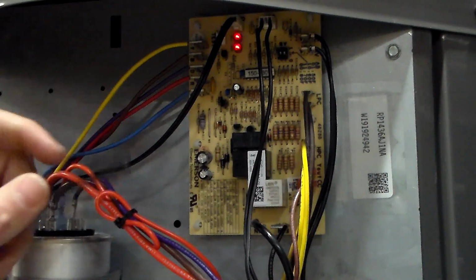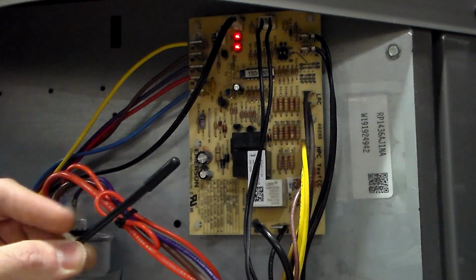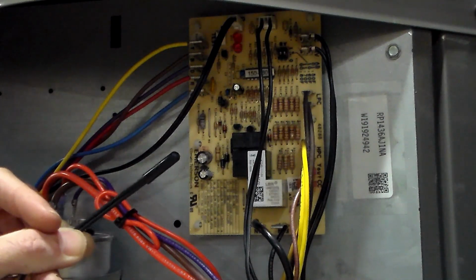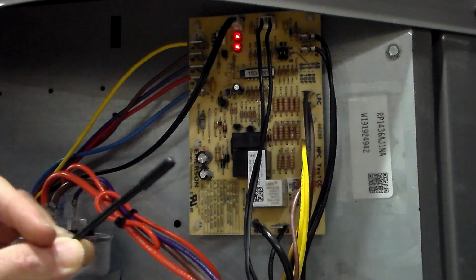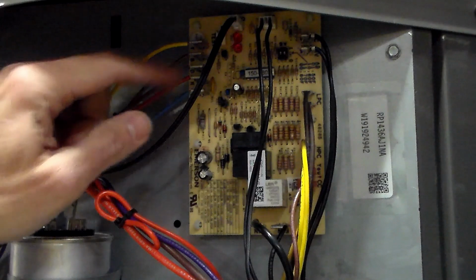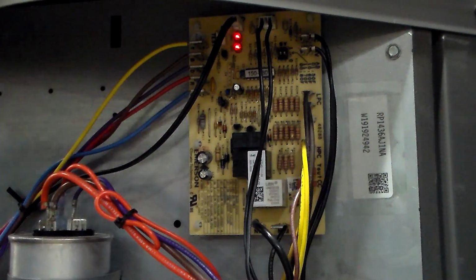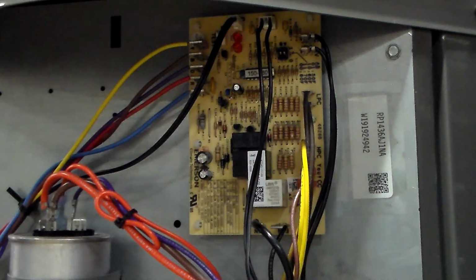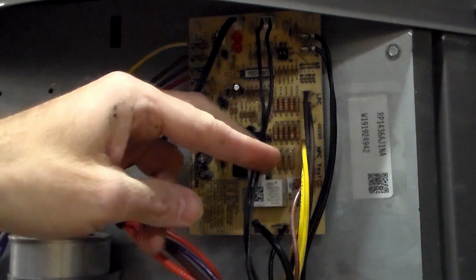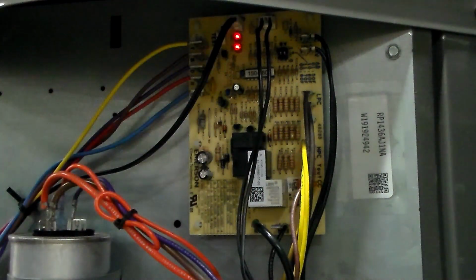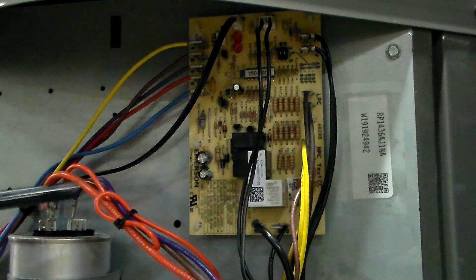Now the first thing I want to point out is this one has the outdoor sensor I was talking about earlier. So this one's going to lock itself out when temperature gets too low outside, and it's going to kick on that backup heat for you. We'll talk about that in a second. We can see that thing's plugged in up here on a clip. I can't see the title of it, but I'll look at the schematic real quick. It's labeled AS, as an ambient sensor. Then we have another one right here that's labeled DS. It's our defrost sensor.